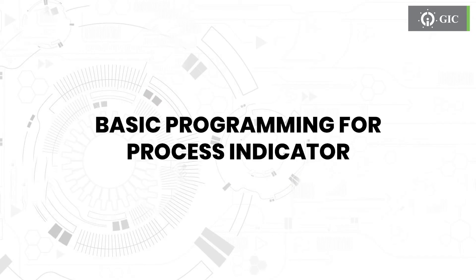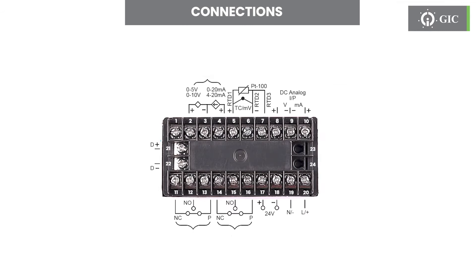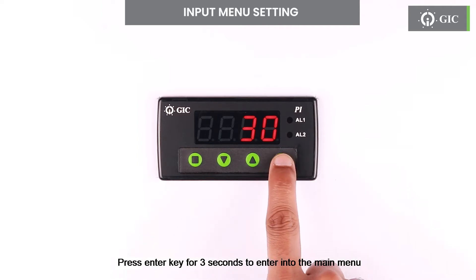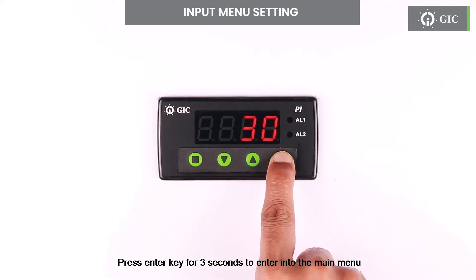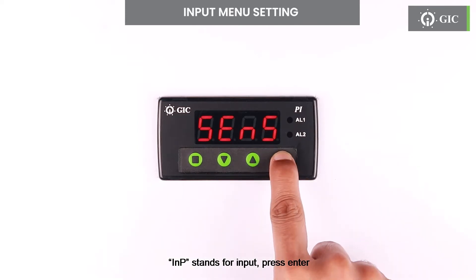Let us see the basic programming for the process indicator. Start and power on the process indicator from default factory settings, after all necessary connections for sensor and power supply are connected. First step is to select input. Press the enter key for 3 seconds to enter into the main menu. INP stands for input — press enter.